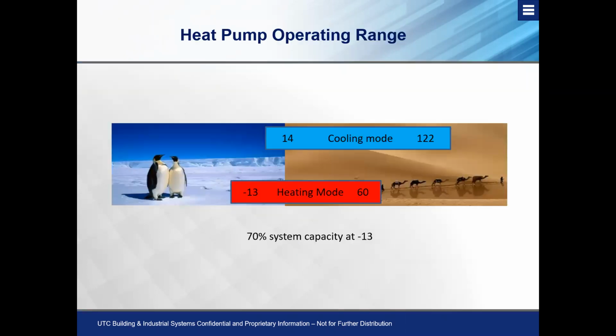Now, let's look at some of the heating operation ranges for our heat pump style system. In the cooling mode, we can go down to 14 and all the way up to 122 degrees. In the heating mode, we can operate down to -13 and then all the way up to 60 degrees.